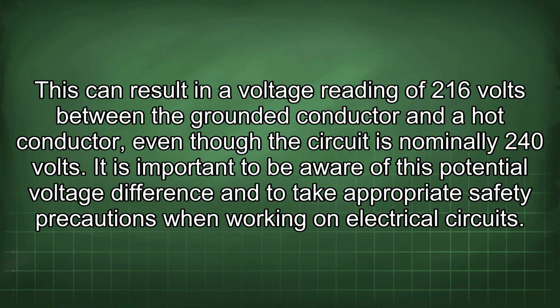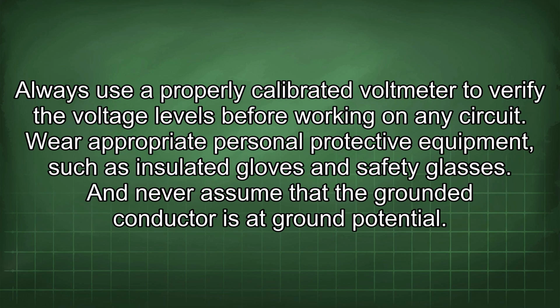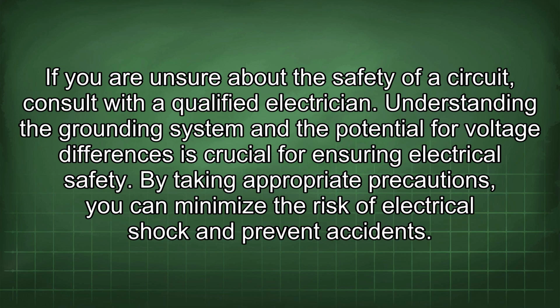This can result in a voltage reading of 216 volts between the grounded conductor and a hot conductor, even though the circuit is nominally 240 volts. It is important to be aware of this potential voltage difference and to take appropriate safety precautions when working on electrical circuits. Always use a properly calibrated voltmeter to verify the voltage levels before working on any circuit. Wear appropriate personal protective equipment such as insulated gloves and safety glasses, and never assume that the grounded conductor is at ground potential. If you are unsure about the safety of a circuit, consult with a qualified electrician. Understanding the grounding system and the potential for voltage differences is crucial for ensuring electrical safety. By taking appropriate precautions, you can minimize the risk of electrical shock and prevent accidents.